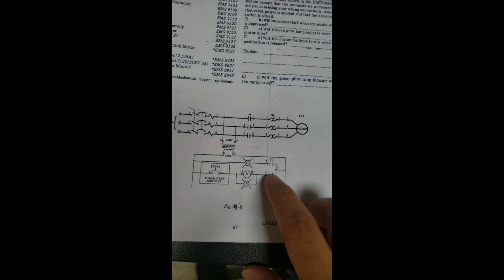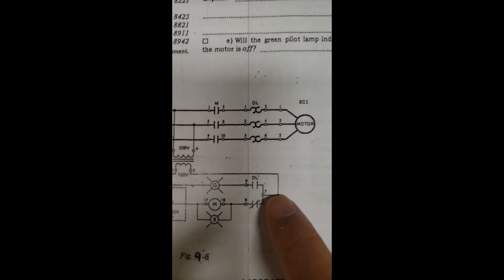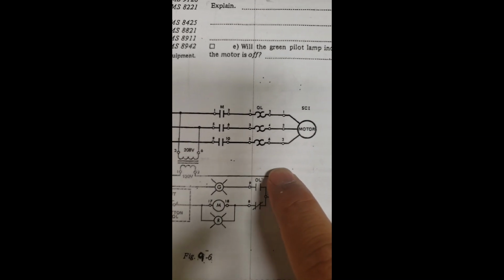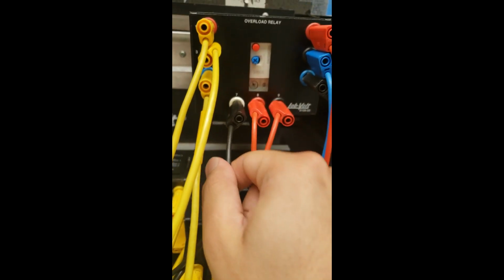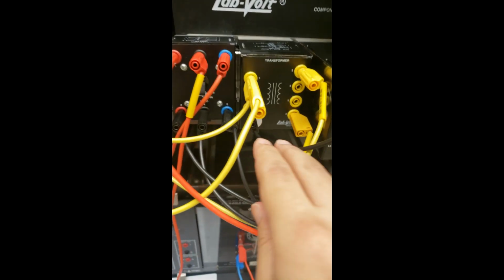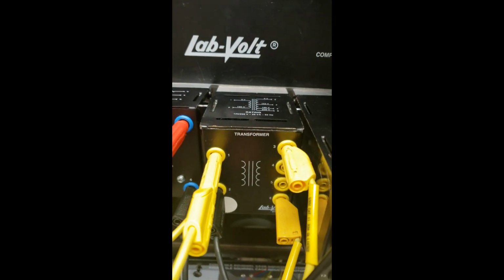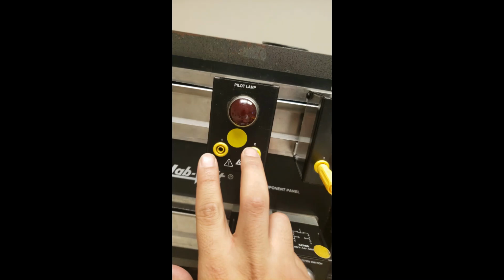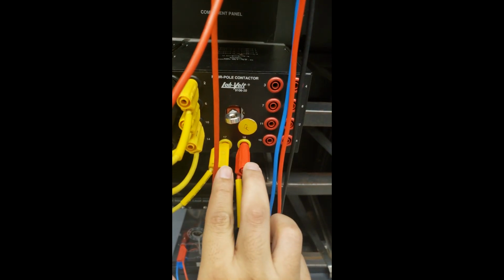Okay, then from the green light, the other terminal of the green light goes to 9 of the overload relay. This one, we've connected to 1, if you remember. The other one is to 9 of the overload. And from 7, the overload relay, to 2 of the transformer. Then I have to connect the red light in parallel to the 17 and 18. The red light will be connected in parallel to 17, 18 of the contactor.